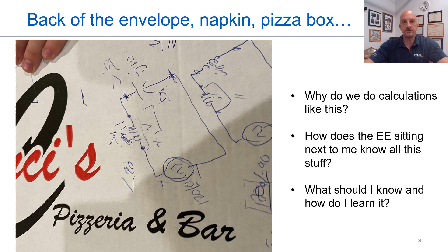In this session, we'll talk about three-phase calculations. So we're going to simplify it to those calculations that are appropriate for three-phase. There will be one or two that are single-phase, but we'll talk about those when they come along. The one thing that's important is really kVA. That's the main equation that we're going to use, from the simple calculations of kVA, including voltage and current, and the square root of 3 where appropriate. We're going to talk about full load amps. How do you size the circuit breaker that comes into a transformer, or goes out of a transformer, or goes into a panelboard or switchboard? And then how do we calculate fault current? And where do we calculate fault current? Breaker sizes and kA ratings for that fault current. And then motor starting and load calculations. The power triangle, one of my favorite things to talk about: kilowatts, kVAR, and kVA. And then power factor correction, and how do we use a one-line diagram to get all that information and put it together.